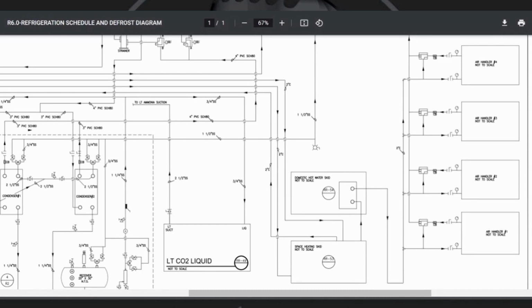At the same time, you open a liquid solenoid on the plus 20 CO2, and you chill the glycol down to the way we sized it, about 33, 34 degrees. And so when you want cooling, you just turn the circulator on, open a liquid solenoid. So all that happens.